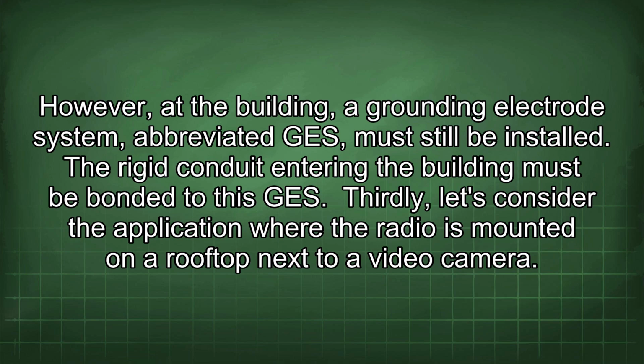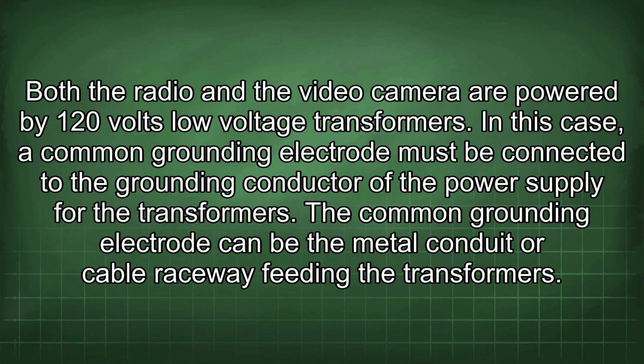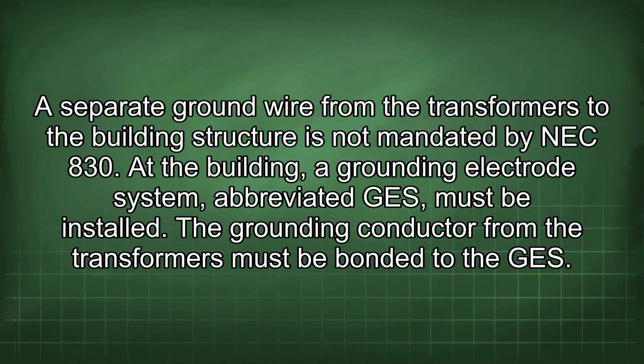Thirdly, let's consider the application where the radio is mounted on a rooftop next to a video camera. Both the radio and the video camera are powered by 120 volts low voltage transformers. In this case, a common grounding electrode must be connected to the grounding conductor of the power supply for the transformers. The common grounding electrode can be the metal conduit or cable raceway feeding the transformers. A separate ground wire from the transformers to the building structure is not mandated by NEC 830. At the building, a grounding electrode system, abbreviated GES, must be installed. The grounding conductor from the transformers must be bonded to the GES.